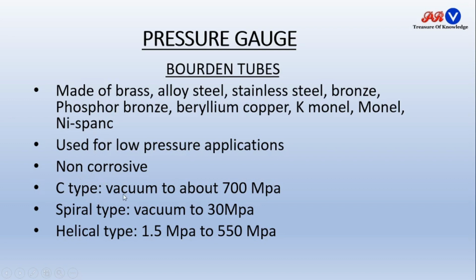C type is used to measure pressure up to 700 megapascal. Spiral type is used for measuring pressure from vacuum to 30 megapascal. Helical type can be used to measure 1.5 megapascal to 550 megapascal.